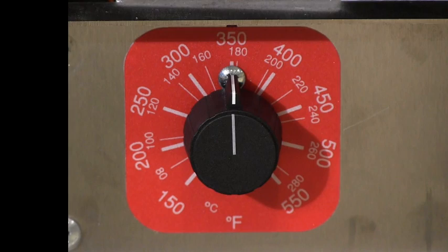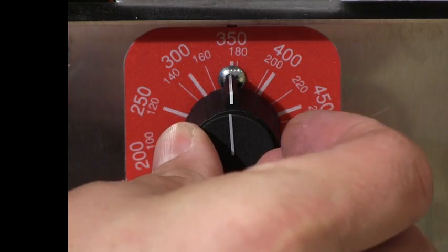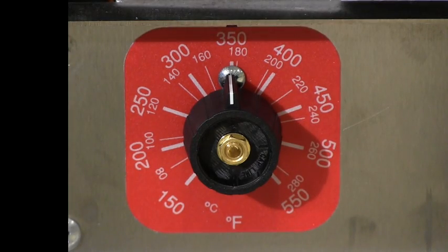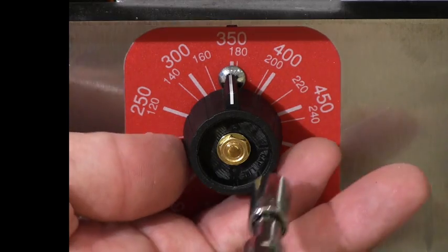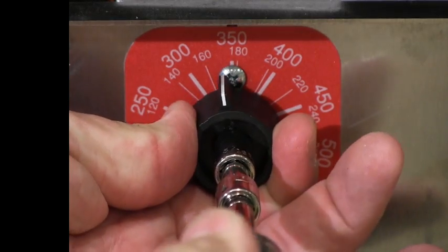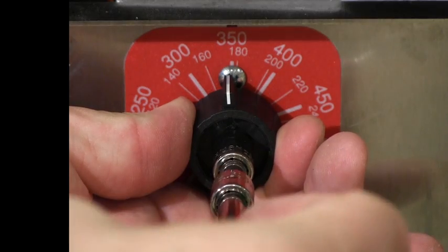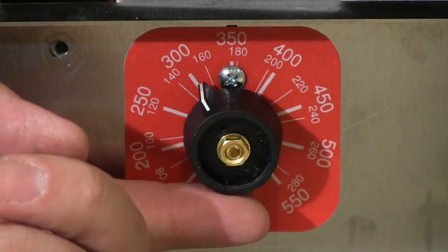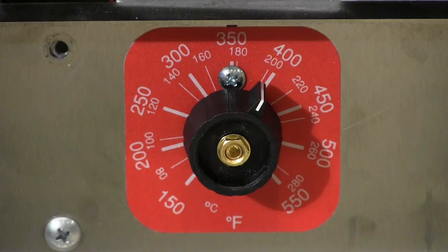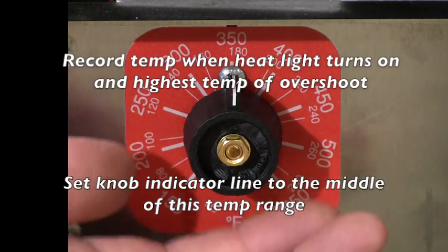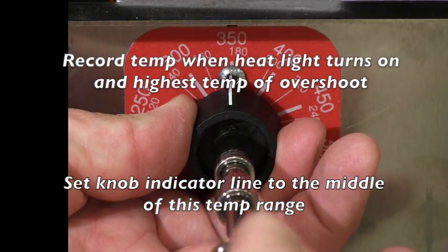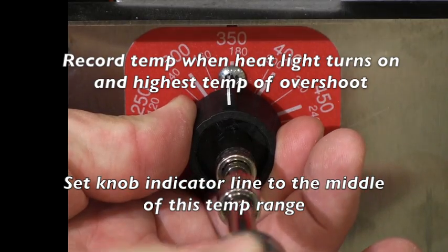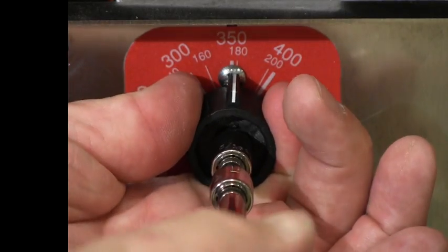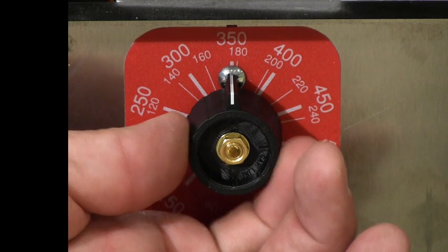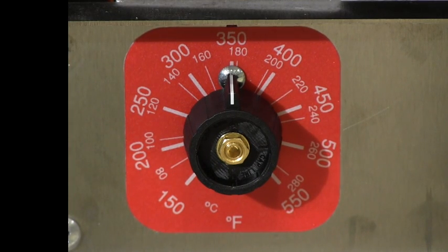If calibration is required, remove the knob cover and set aside. Hold the knob tight and carefully loosen the 5/16 inch nut in the middle of the knob. Once the nut is loose, you can now move the indicator line on the knob to match the average temperature between the low and the high cycling temp for that heat zone. Once set correctly, hold the knob securely, retighten the nut in the middle of the knob, and allow the heat zones to cycle several times to verify your changes.